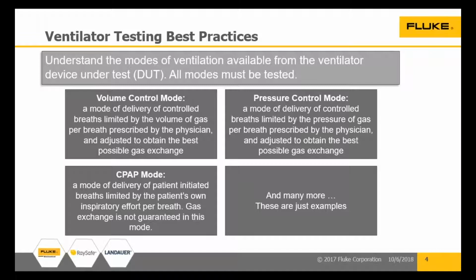So in our older test instruments, the way we did it is we set a breath detection threshold. And that threshold could be increased or decreased. The default value was about 2 liters per minute so that we could figure out how to count the breaths. And for 99.9% of all of the ventilators at the time, including the BiPAP units, we were able to get the breath rate count correct. That was critical because that's how we figured out the timing for inspiratory time and expiratory time, which you need to get to IE ratio properly.